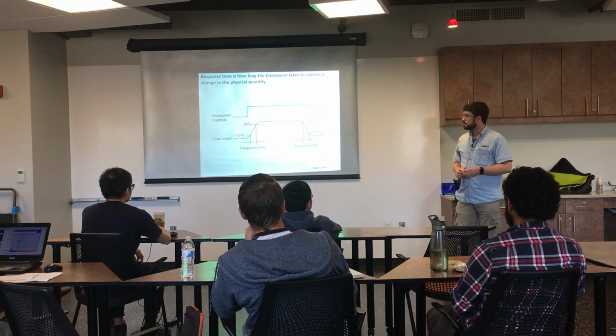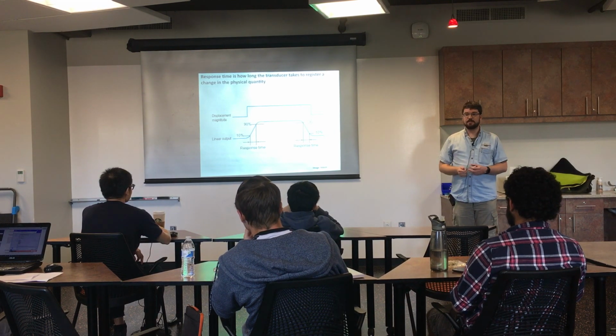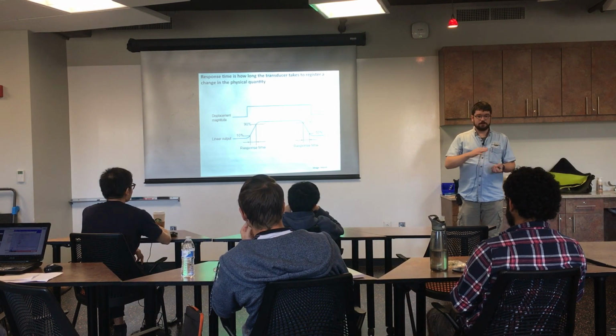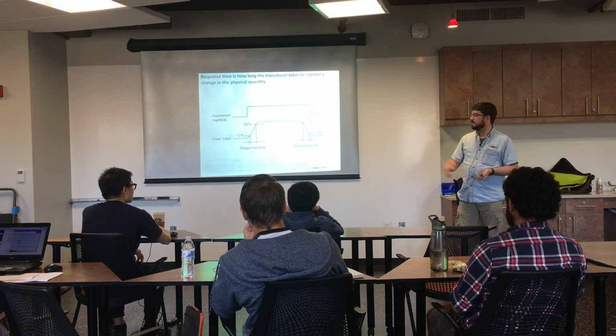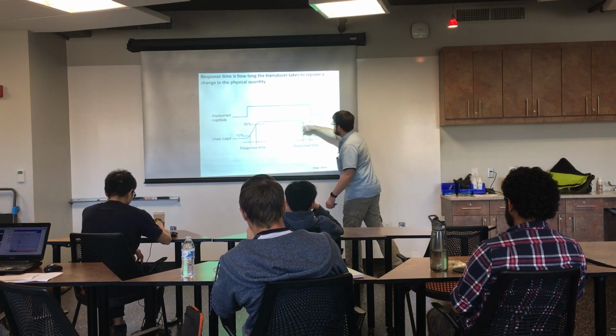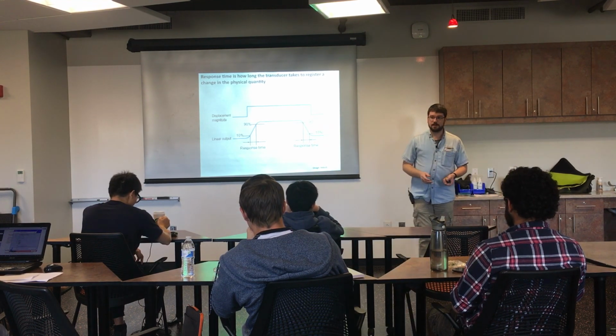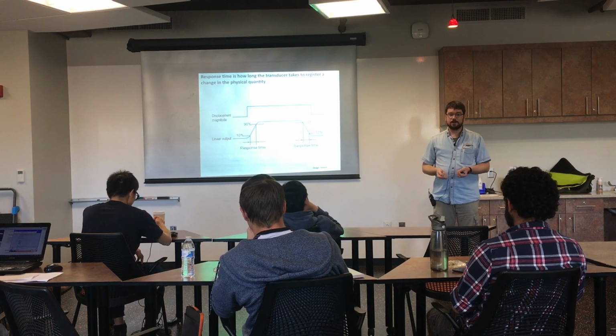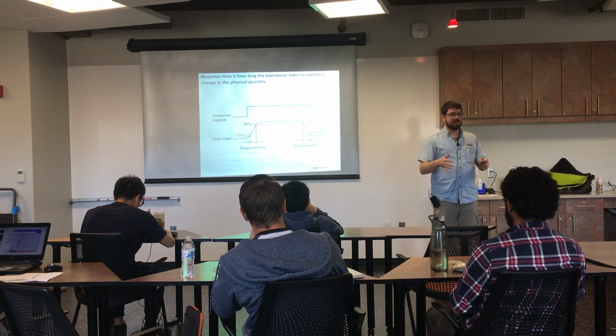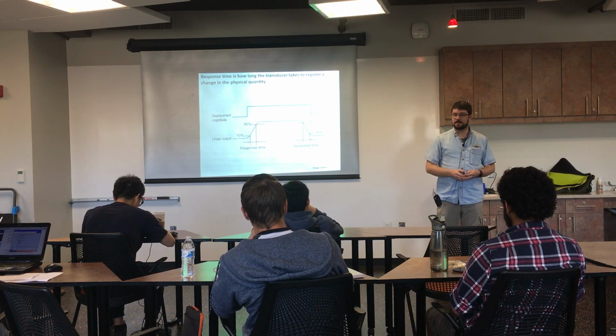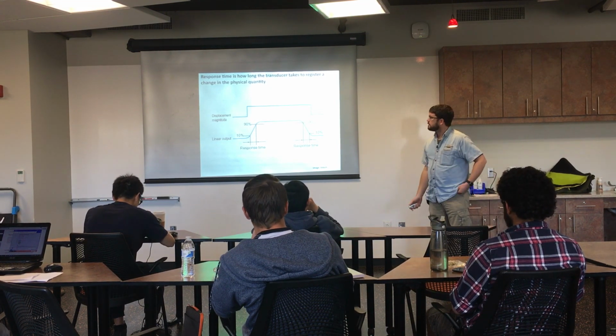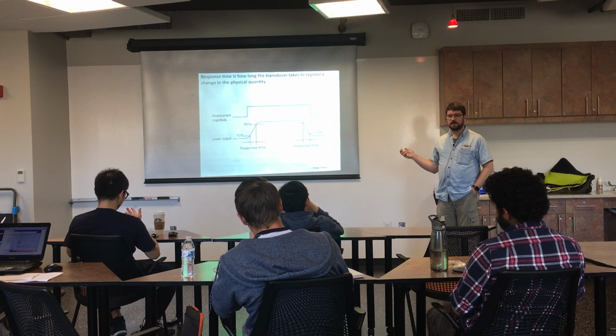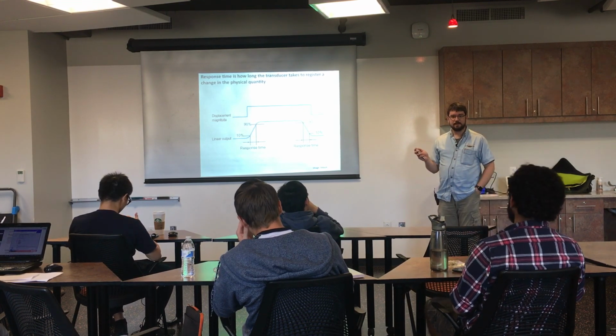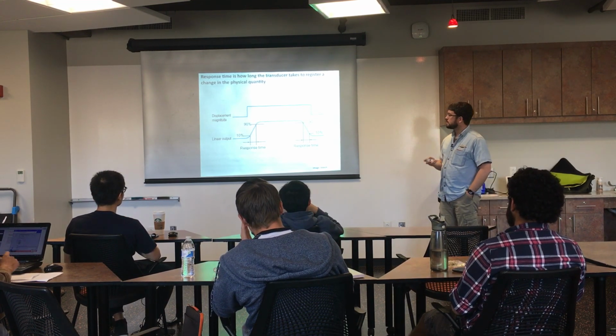It's specified differently for pretty much every manufacturer and every transducer. Some people do, it takes this long to get to 100%. Some people do a 10 to 90% response time. You just have to look, and it makes comparing transducers very hard because you generally have to convert all the manufacturer's units to one standard unit when you're doing your comparisons. Same with linearity, really. Does response time make sense to everybody? Takes a little while to see effect. Okay.